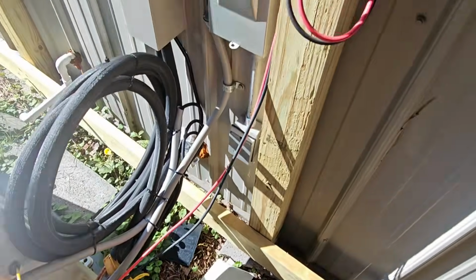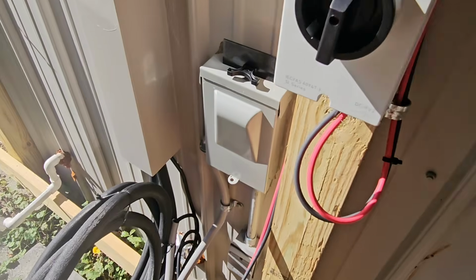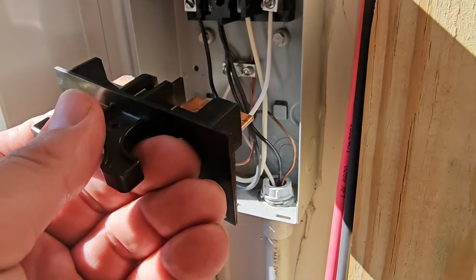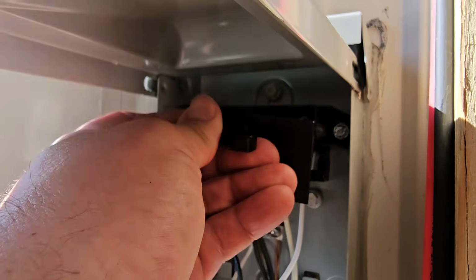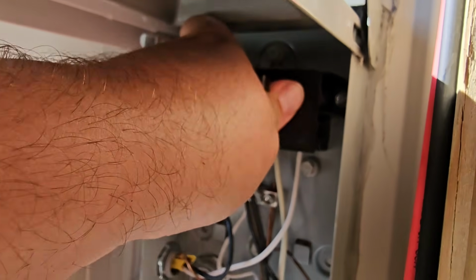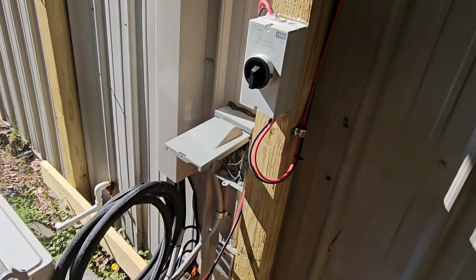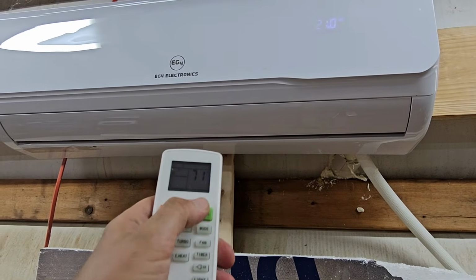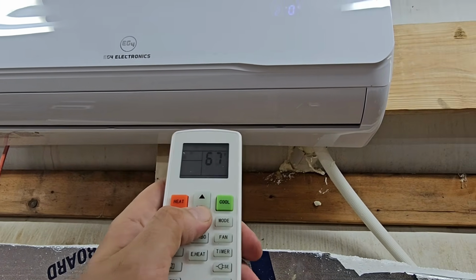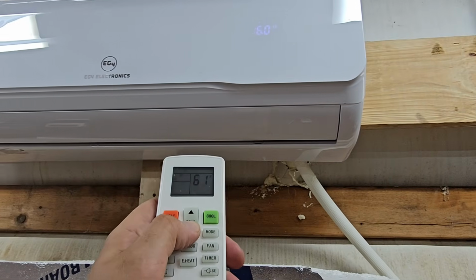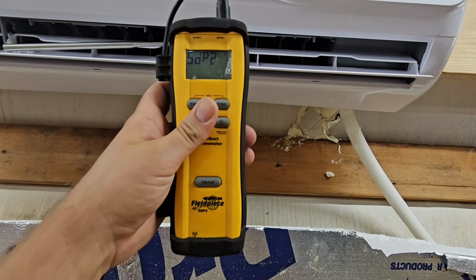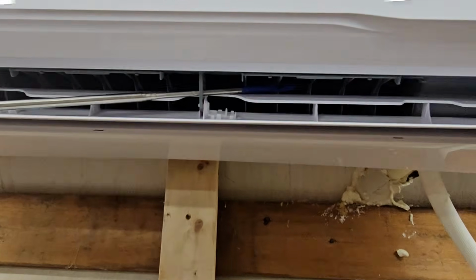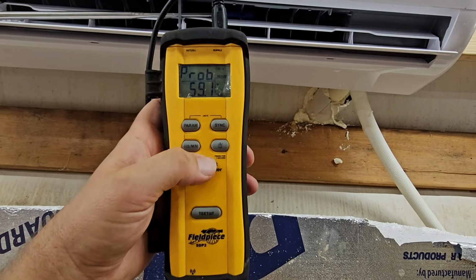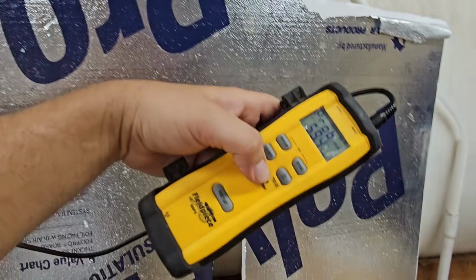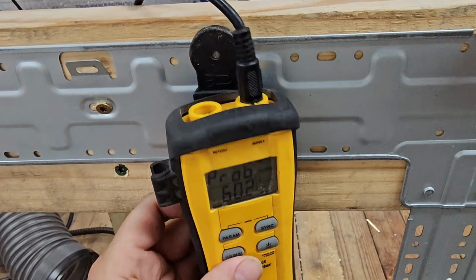I'm going to go ahead and turn my PV power on, my AC power, plug the disconnect in. Let's go turn the unit on. Turn the unit on cooling, temperature down all the way to 61. I'm placing my dual induct psychrometer inside the up and down vane area. That way I can measure the temperature. And I'm going to leave this right here.